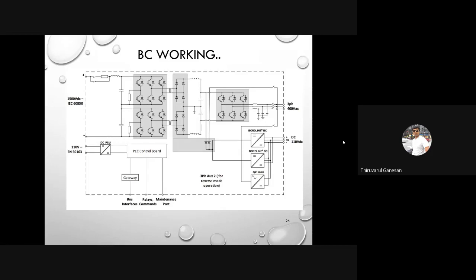So it is mainly on the high inductive side. If it is on the high inductive side, your upcoming circuit will be protected. For example, you have the traction converter inverter portion after your catenary system. You want to isolate and protect your traction converter from high current or current ripple. You have to go for an inductor, irrespective of whether it is AC or DC. In a DC system, as per the standard, it has to follow some tolerances, but nevertheless it will be used based on your customer requirement and the application.